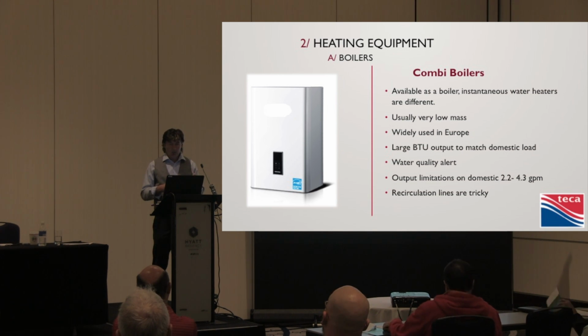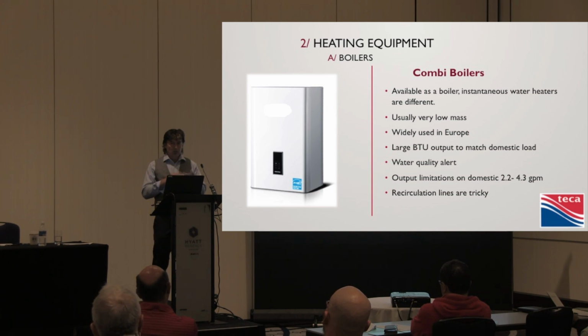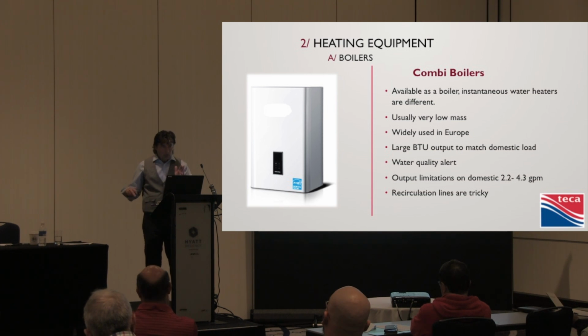In those heat exchangers. I mean, in a closed loop system, you fill it once, and really you don't want to fill a system with hard water, but you've got a closed loop. You're not introducing this hard water all the time. When you're putting domestic water through an instantaneous heater, whatever's in it, you're doing it every time. So they have little filters on these things.